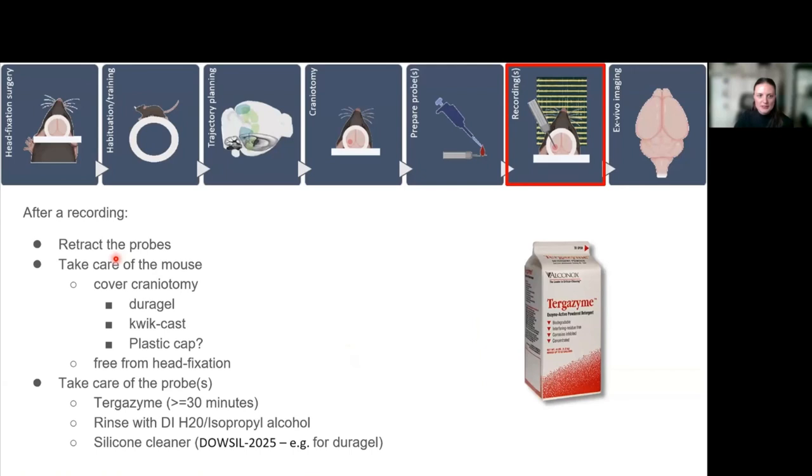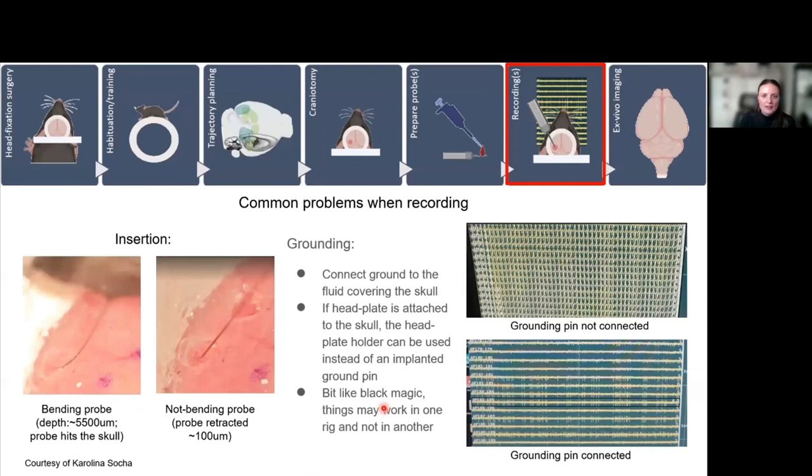After the recording, you have to retract the probes. As soon as you can, take care of your mice, make sure that they're okay, cover the craniotomy with the three things I just discussed, and free them from head fixation. Then you can take care of the probe. It's good to wash it with tergazyme first, which degrades the biological tissue stuck to the probe. Then we usually use deionized water or isopropanol alcohol to rinse it. Like I said, sometimes the DuraGel sticks to the probe and we use silicone cleaner for this.